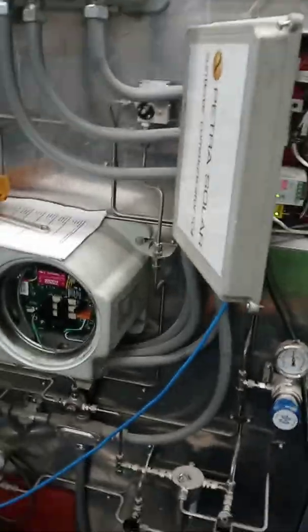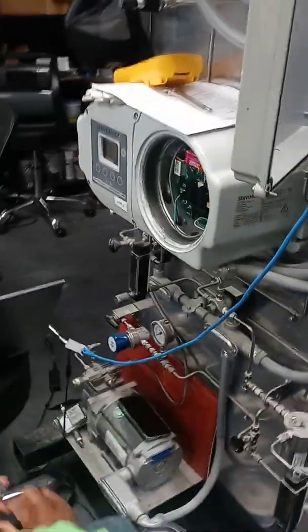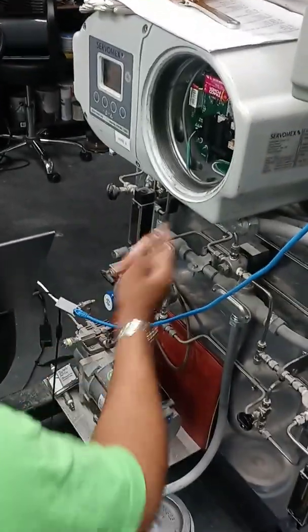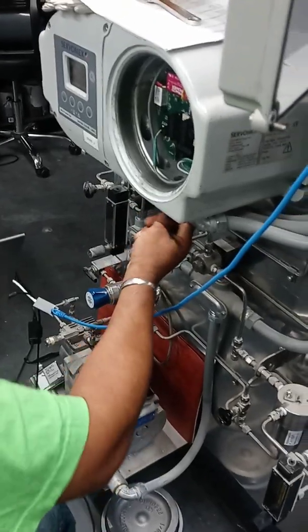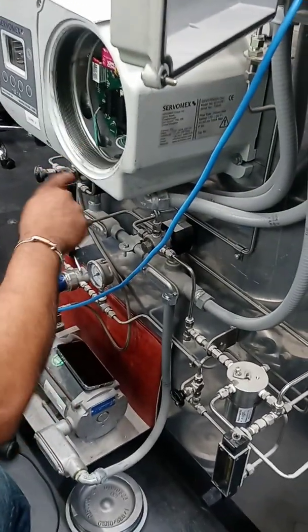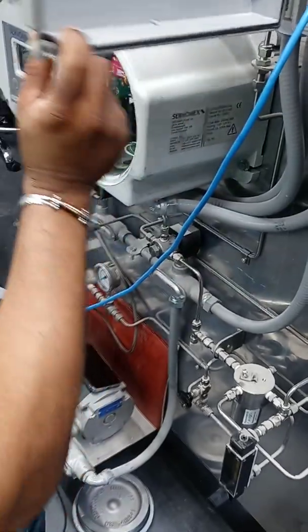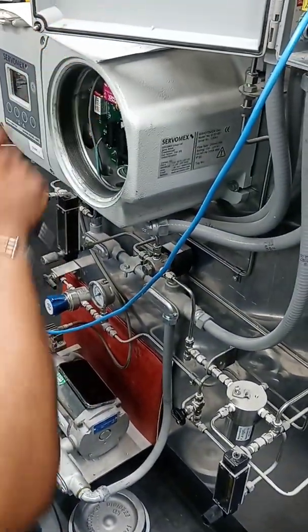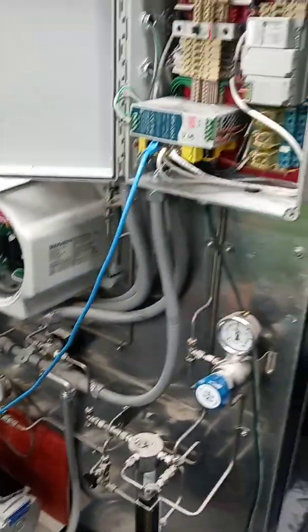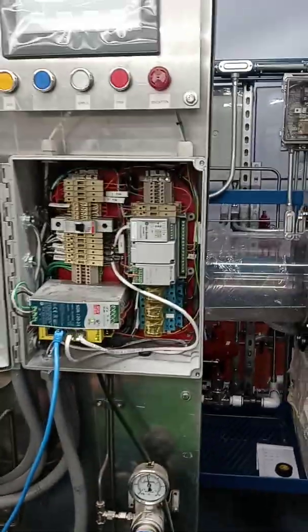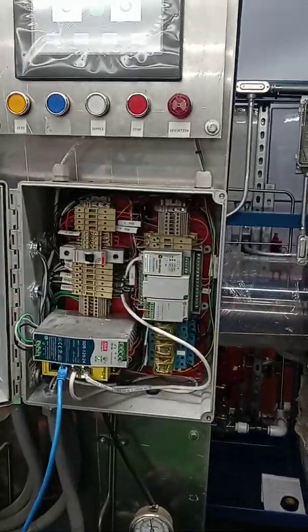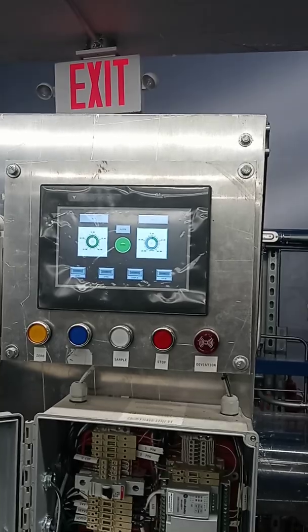Servomex 1900 — this is exactly as you would see it in the field. You would normally have some type of vacuum pump pumping the sample from a heater, generally, or some type of burner application, or it could come just from the atmosphere. Then it will go into a control system and the operators will be able to see it.